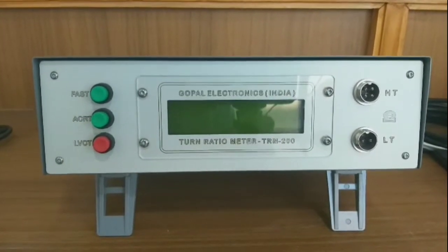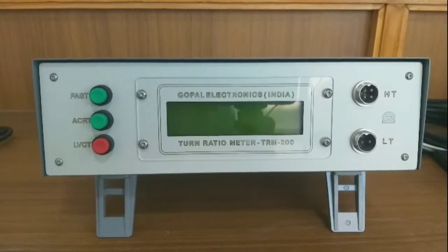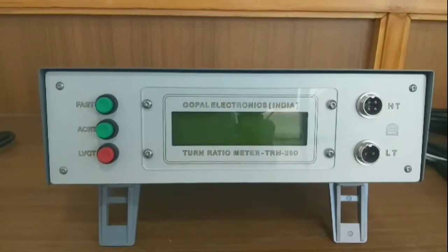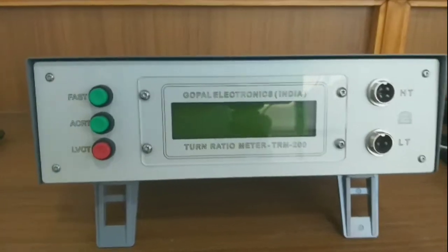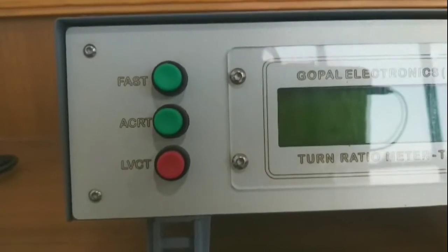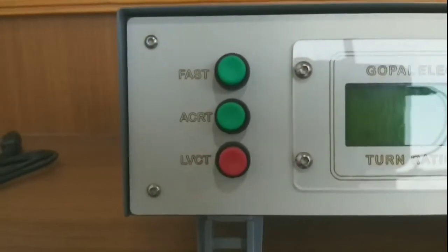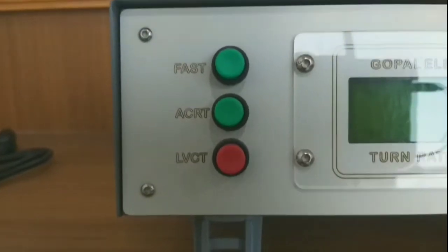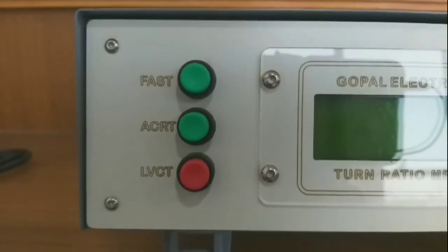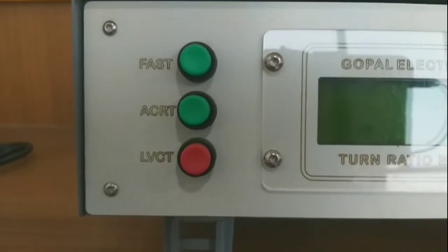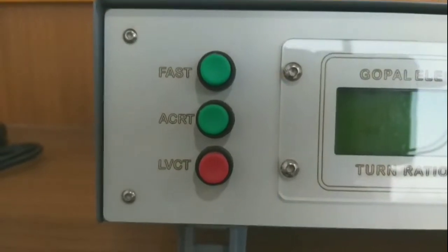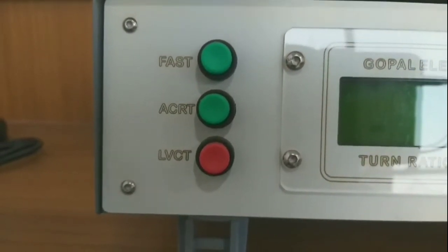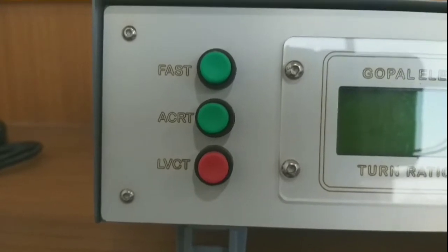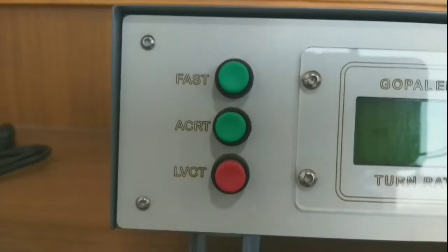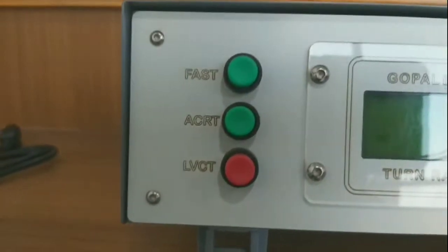This is Gopal Electronic's single phase transformer turn ratio meter. In this video, I will show you how it works. You can see that here we have provided three buttons for three different modes of testing: fast mode, accurate mode and LVCT mode. In fast mode, it gives a quick result within 2 to 3 seconds at low accuracy. In accurate mode, it applies all mathematical filters and gives the result at standard accuracy. LVCT is for when you want to check short winding or to test CT.